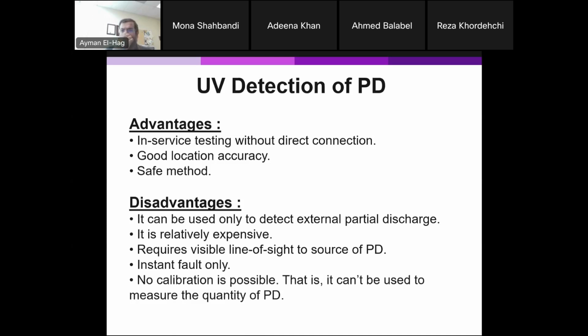Now, this technique and the other technique have no calibration. So you don't actually measure the quantity of the partial discharge. It is all relative. This is unlike the classical method we mentioned two weeks ago. That one will give you the partial discharge in picocoulombs, so it's calibrated, although it does not give you 100% the amount of discharge inside the assets. It's called apparent charge. It gives you some numbers.